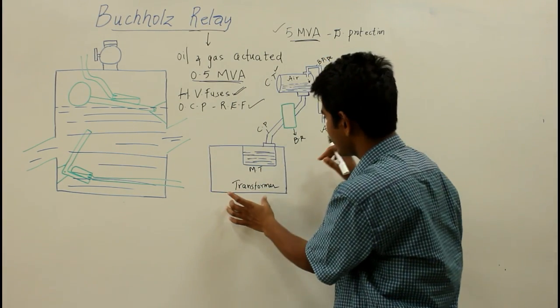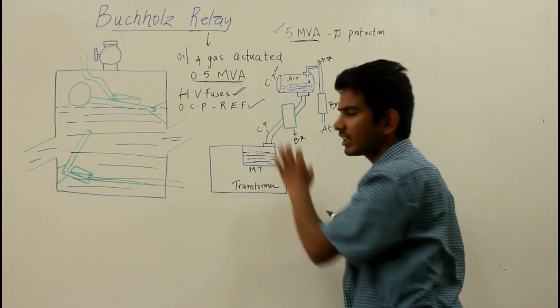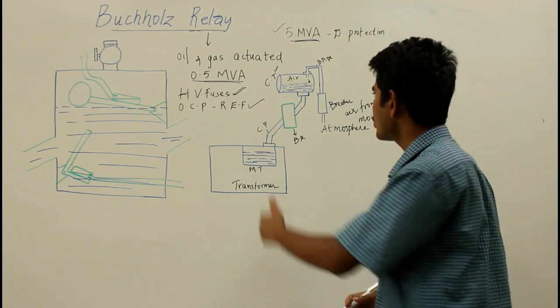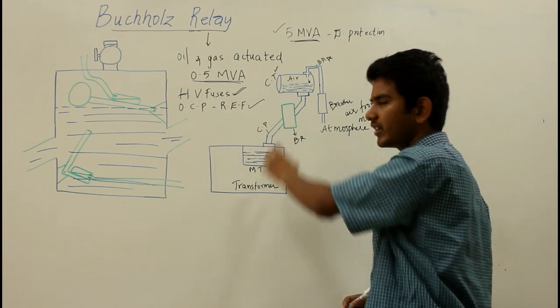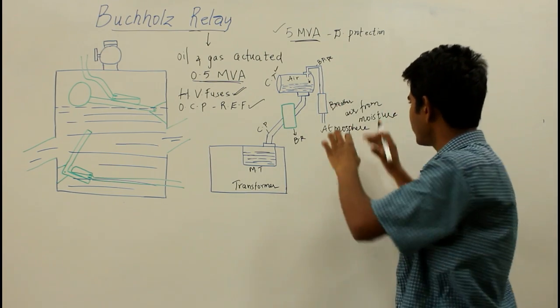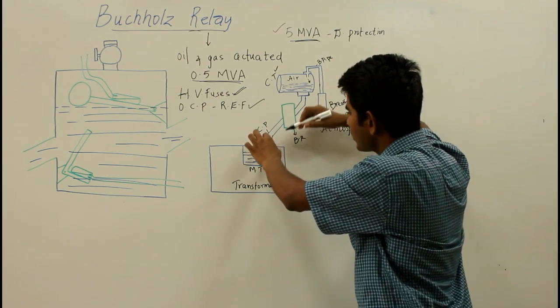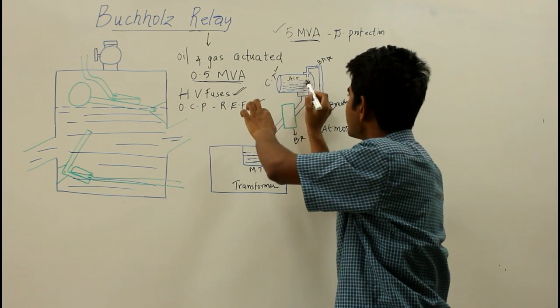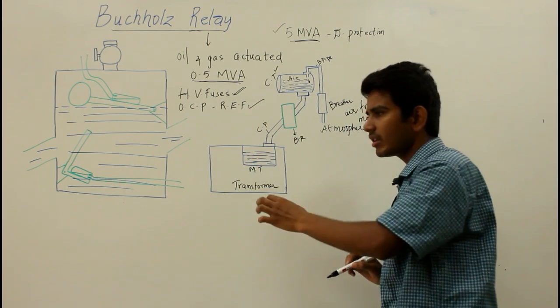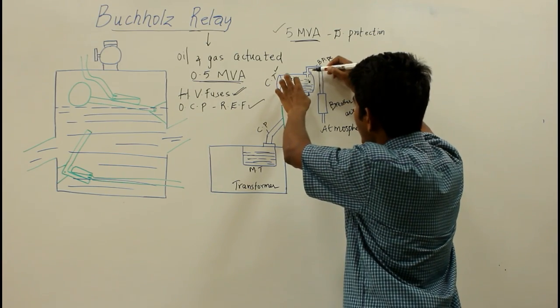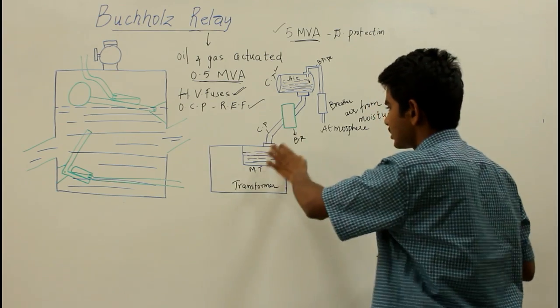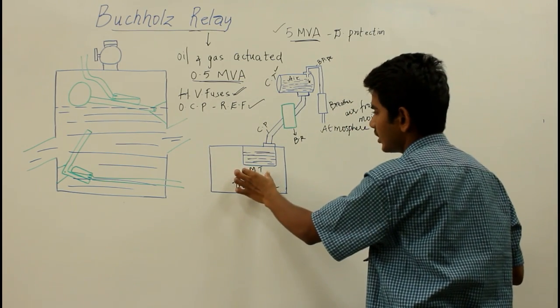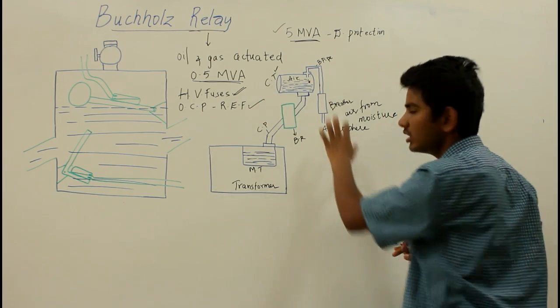This is the overall connection layout of the transformer: showing where the Buchholz relay, conservator tank, and breather are located. If asked about the conservator tank's purpose: whenever the transformer is overloaded, it provides adequate space to the expanded oil. The breather filters the air from moisture. Whenever the oil temperature increases, the oil expands, and when operation returns to normal, the oil level falls and air accumulates in that space.